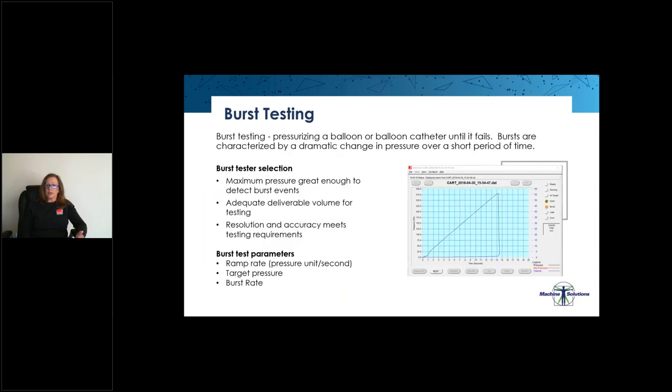Burst testing is the pressurization of a balloon or balloon catheter until it fails. Bursts are characterized by a dramatic change in pressure over a short period of time. It's important to use the right tool or piece of equipment to get a job done accurately and correctly, and selecting a burst tester is no different.